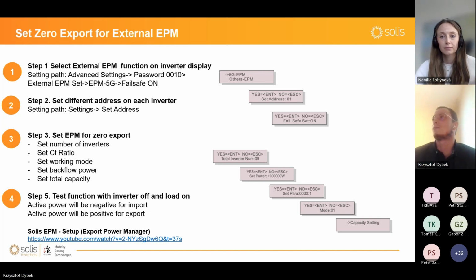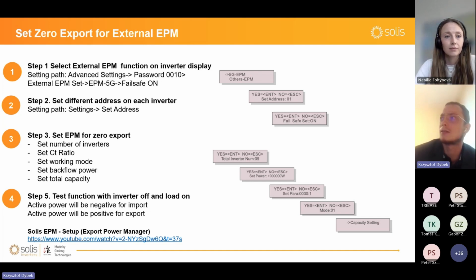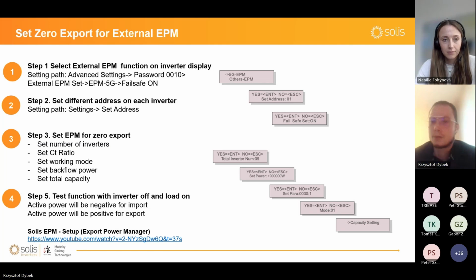This is very important. And what is it, this failsafe? So inverter is checking every 5 seconds about the signal from EPM, because EPM will communicate with the inverter within each second. But if for 5 seconds there is silence, inverter will shut down and stop production to avoid sending anything to the grid if this failsafe is on. So I highly recommend to set it on. Otherwise, if you leave it off, nothing will be broken, but inverter will be no longer limited by EPM. It will put out whatever it can produce.